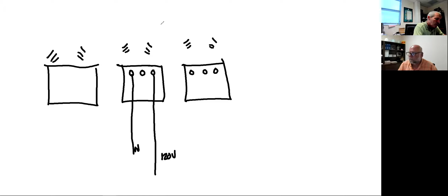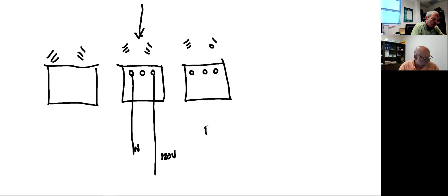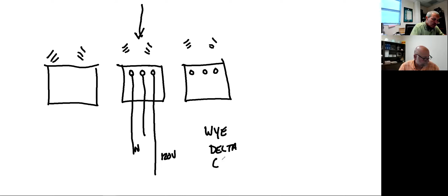I've got a transformer with 3 bushings, but I only have 2 wires coming out of the center. Is that a Y? Y, correct. That center transformer, when you have 3 transformers in a bank, I like to call it a primer. It's the indicator of the difference between closed delta and open delta. 2 wires out of the center transformer means Y. 3 wires out of the center transformer means delta, and closed at that, if you have all 3 transformers.